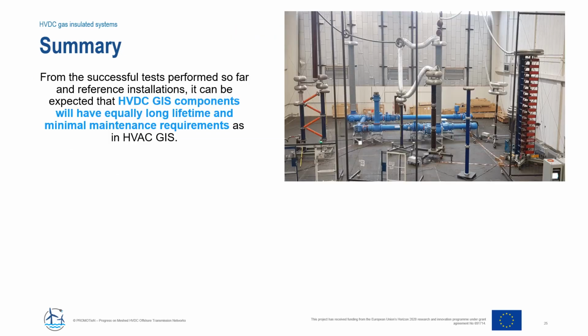And again, summarizing from the tests, it can be expected that HVDC GIS components will have equally long lifetime as known from HVAC GIS. Using GIS technologies, the space requirements for an HVDC switchgear can be reduced by 70 to 95%, leading to lower costs.